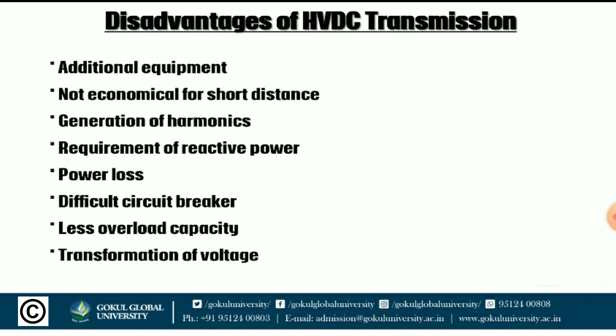Next is a difficult circuit breaker. It means the DC circuit breaking is very difficult in multi-terminal HVDC system. Next is a less overload capacity. It means the overload capacity of the converter used in the HVDC system is very less. And last one is the transformation voltage. It means as the transformation works only on the AC supply, the DC voltage cannot be raised up for the efficient high voltage transmission very easily.